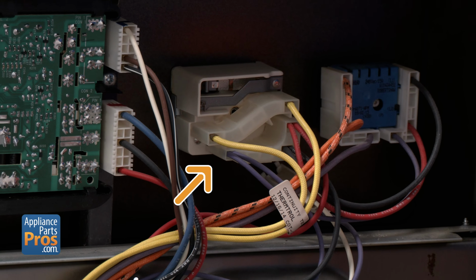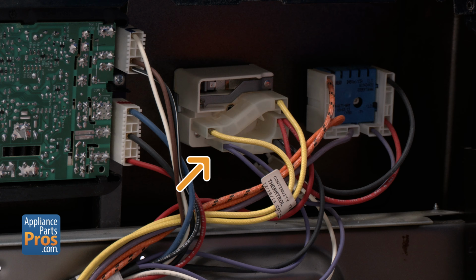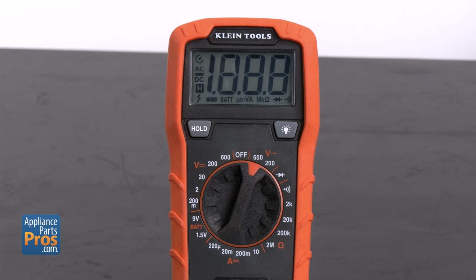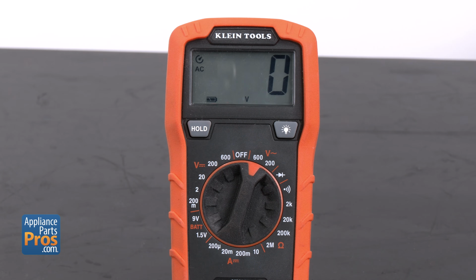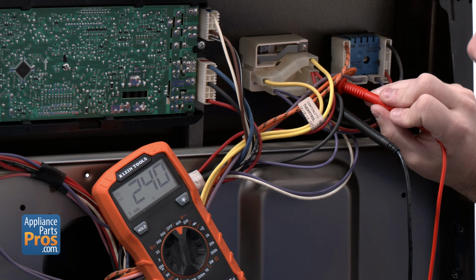We're testing the small single element switch, but the same terminal locations would be used for the large elements as well. Set your multimeter to volts AC, indicated by a V with a squiggly line. Place one probe on the black wire at terminal L1 and the other probe on the red wire at terminal L2. You should see about 240 volts AC.